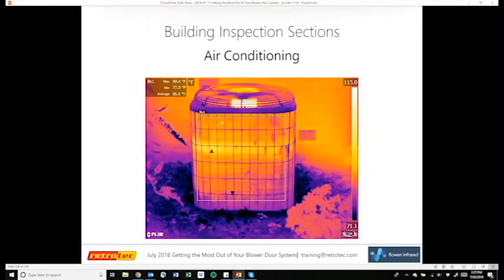So air conditioners fit right into that HVAC. What's that condenser looking like, both visually and thermally? And we can make a correlation to efficiency simply by looking at the thermal picture of this condenser. And if these fins are not clean or combed out correctly, the efficiency of this unit drops considerably and would show up as increased heat at the condenser level.